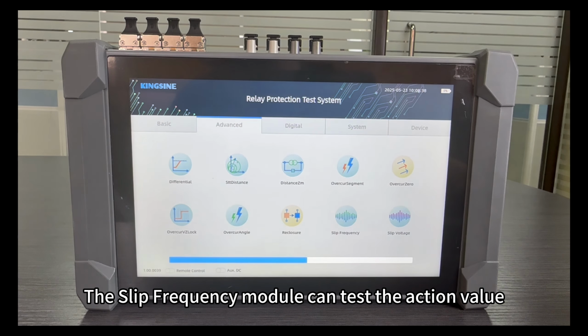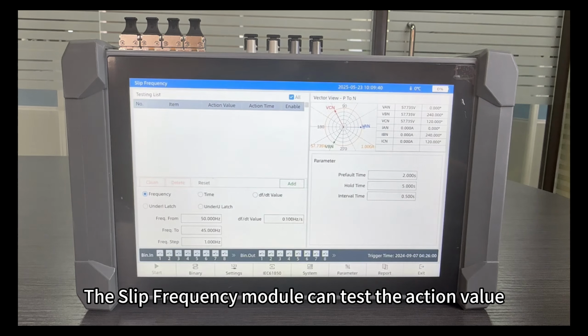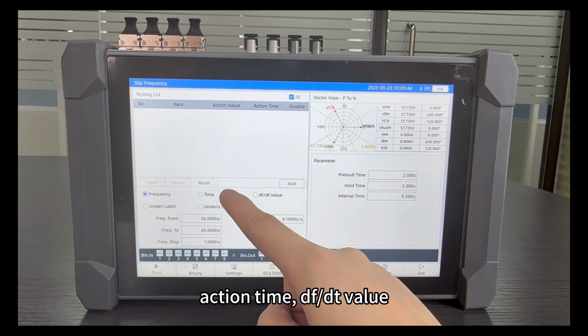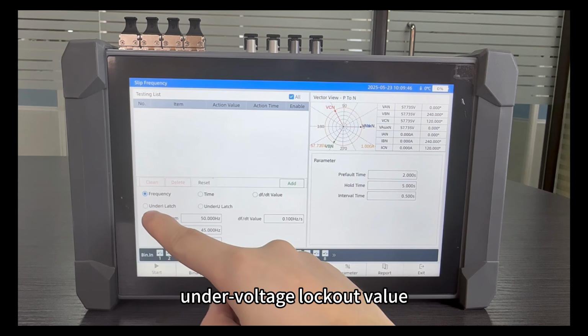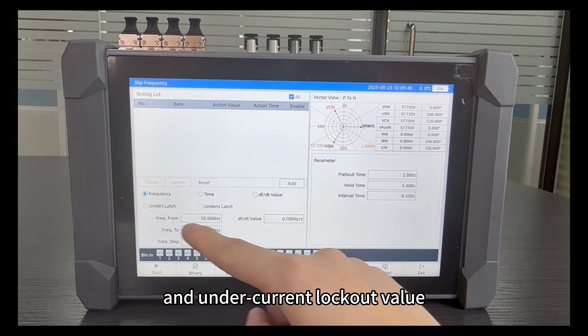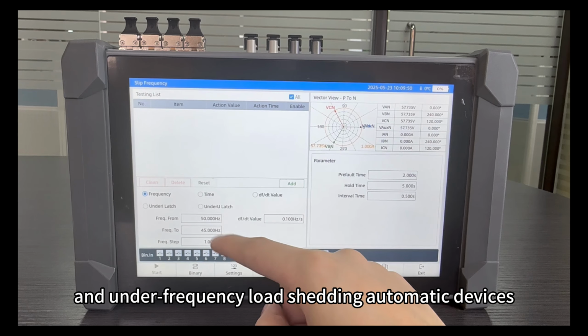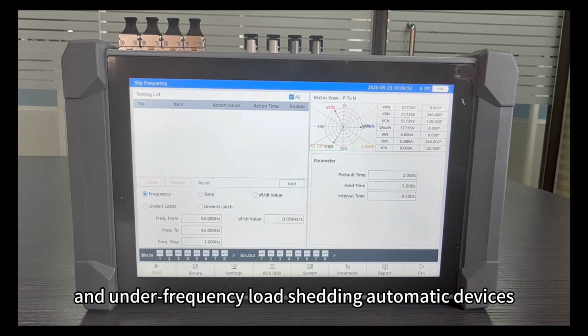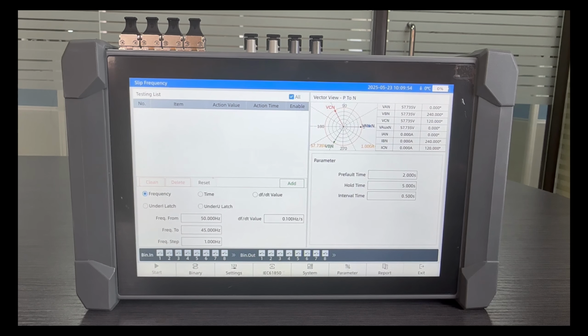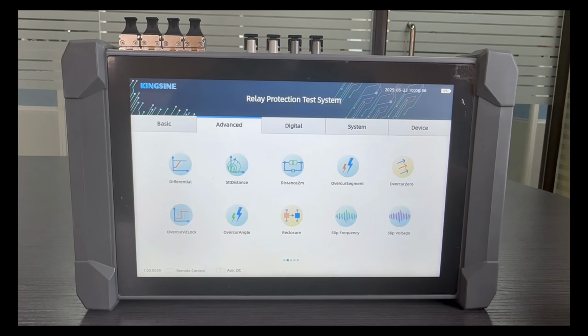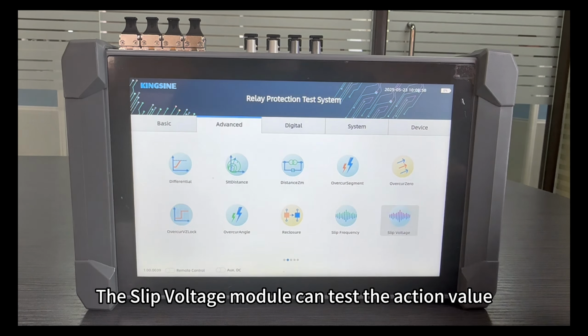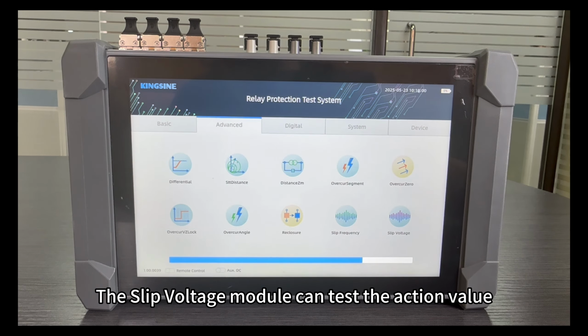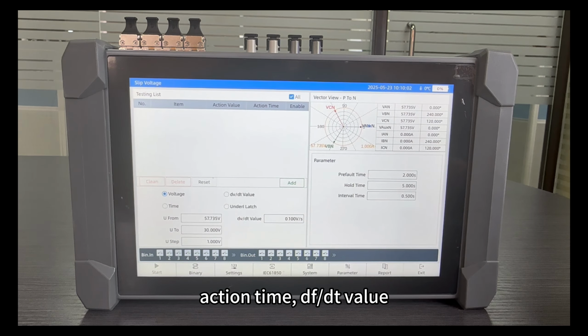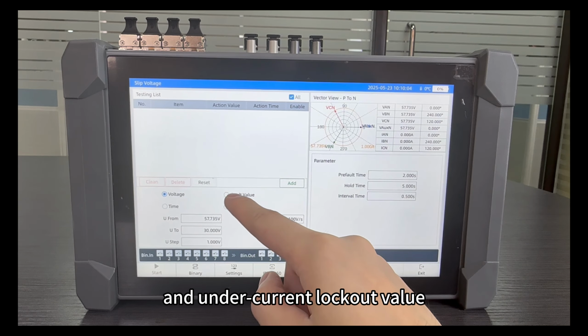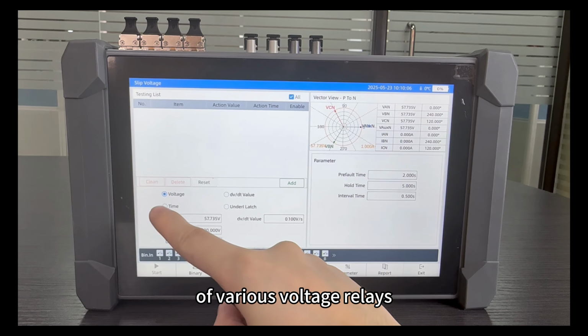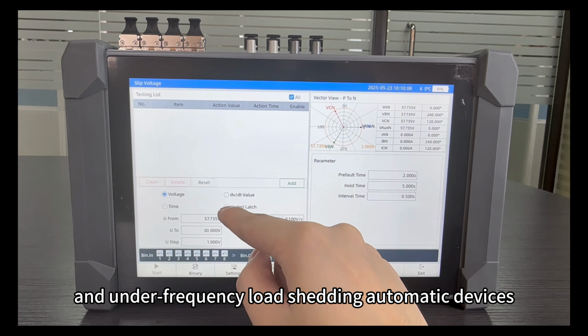The slip frequency module can test the action value, action time, DF/DT value, undervoltage lockout value, and undercurrent lockout value of various frequency relays and underfrequency load shedding automatic devices. The slip voltage module can test the action value, action time, dv/dt value, and undercurrent lockout value of various voltage relays and underfrequency load shedding automatic devices.